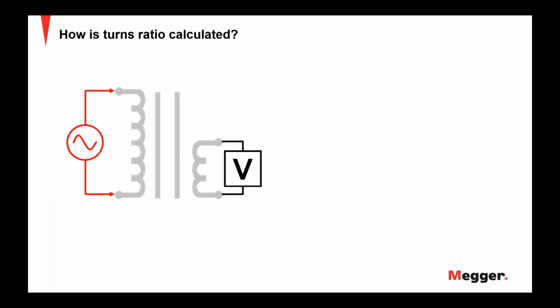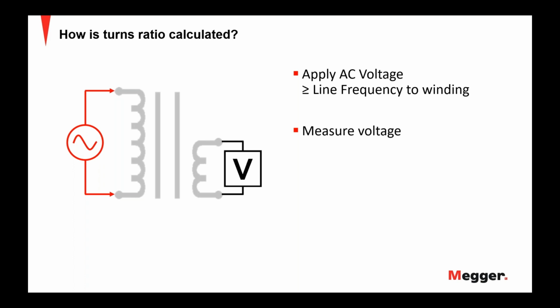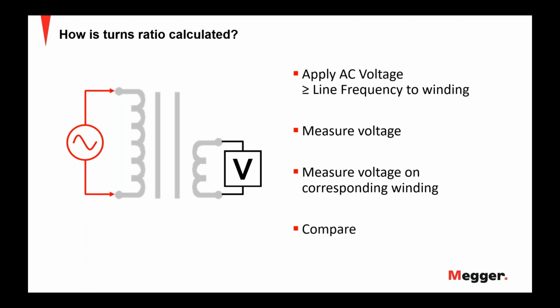When we talk about turns ratio testing, it's a very simple test to perform and to understand. And the way that it is performed is that we apply AC voltage that's greater than or equal to the line frequency to the primary winding. We then measure the voltage that's induced on the secondary winding. In this fashion, typically the voltage is reduced on the secondary winding, or stepped down as we refer to it. But then what you will do is you will just compare the voltages that you injected and the voltages that you measured, and that is your turns ratio. And then along with the nameplate, if you were to enter that into the device, it would give the percent error to that 0.5% limit that I discussed earlier.